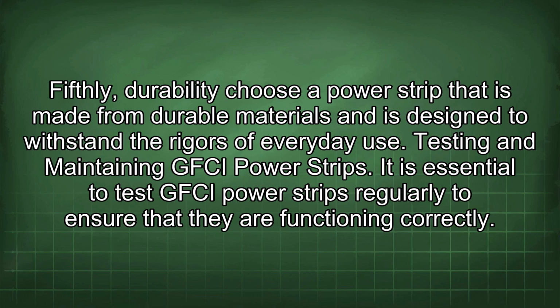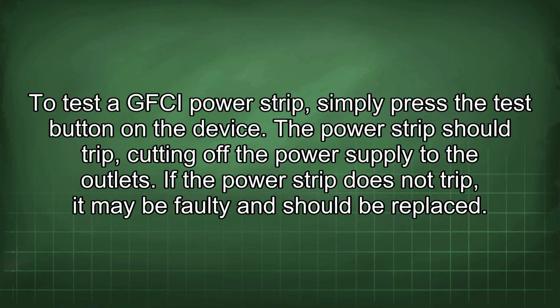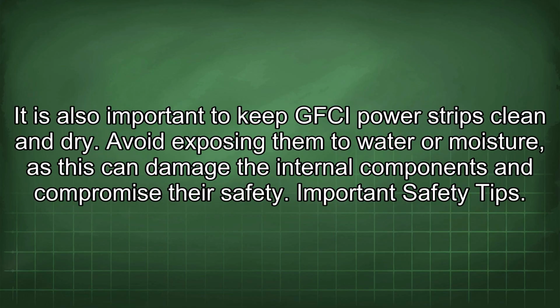Testing and maintaining GFCI power strips. It is essential to test GFCI power strips regularly to ensure that they are functioning correctly. To test a GFCI power strip, simply press the test button on the device. The power strip should trip, cutting off the power supply to the outlets. If the power strip does not trip, it may be faulty and should be replaced. It is also important to keep GFCI power strips clean and dry. Avoid exposing them to water or moisture, as this can damage the internal components and compromise their safety.